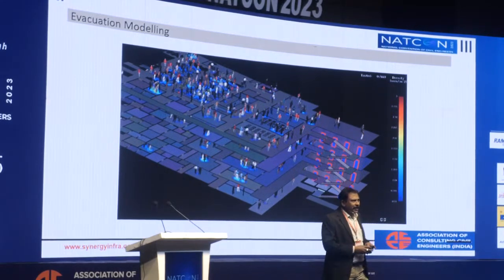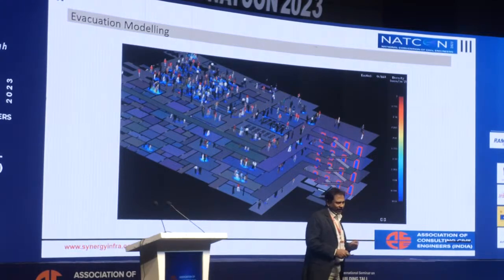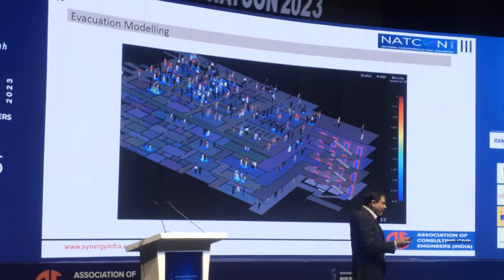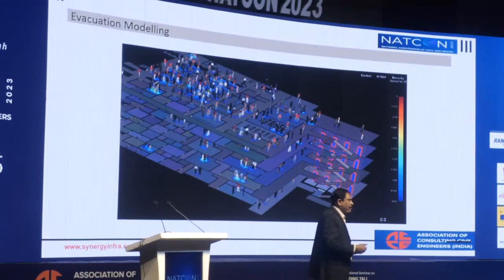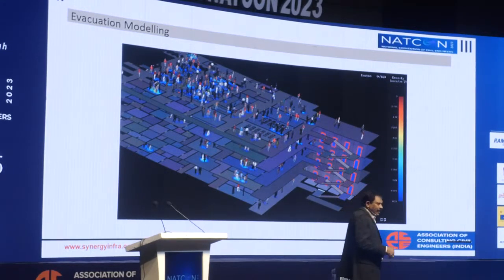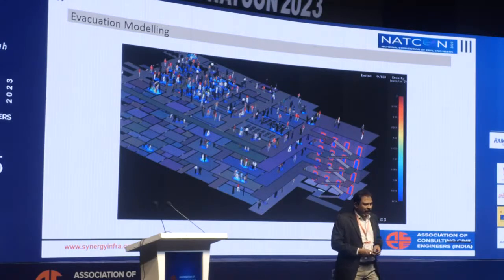Then he wanted us to certify whether our staircases are good enough or not. So this is another problem. We have 2-meter wide staircases, even though for office buildings the minimum needed is 1.5 meters, and staircase width has been worked out based on 10 mm per person, based on NBC. NFPA says 7.5 mm per person. Since he's an American client, we read this.